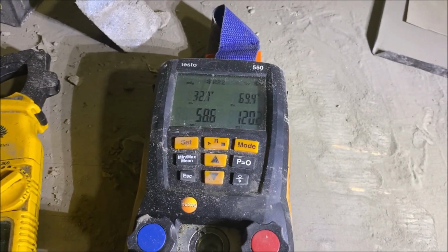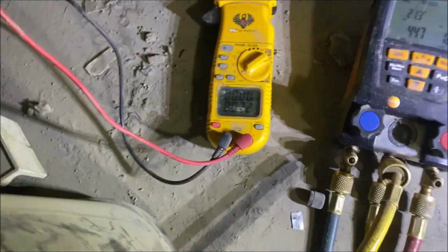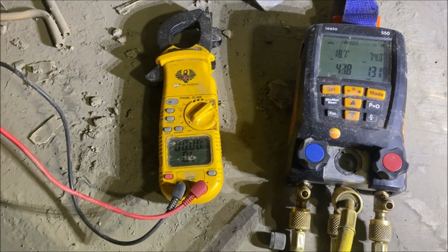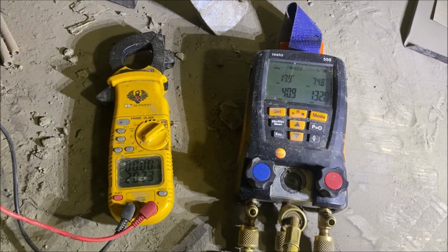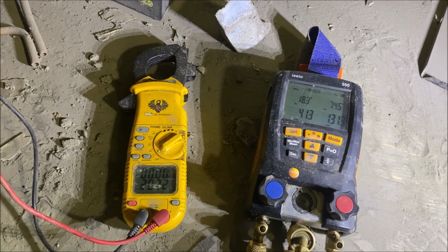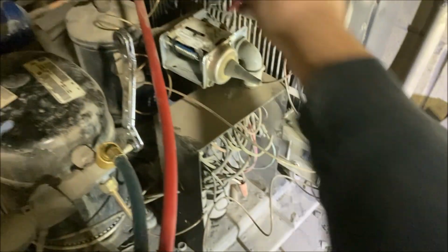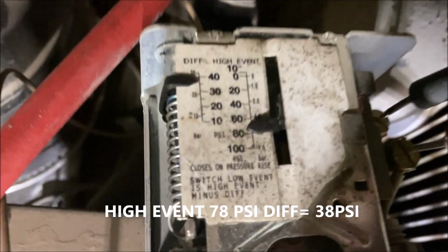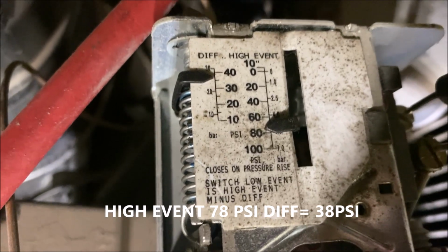All right, so right now it is running, as you can see, and it's going to pull down, and we're going to go off on low pressure switch. We're going to check for potential difference on our pressure switch, and you're going to see we shut off and we have line voltage, which is 202 volts across the contacts. That's telling us our pressure switch is open. And here's what our pressure switch is set to.